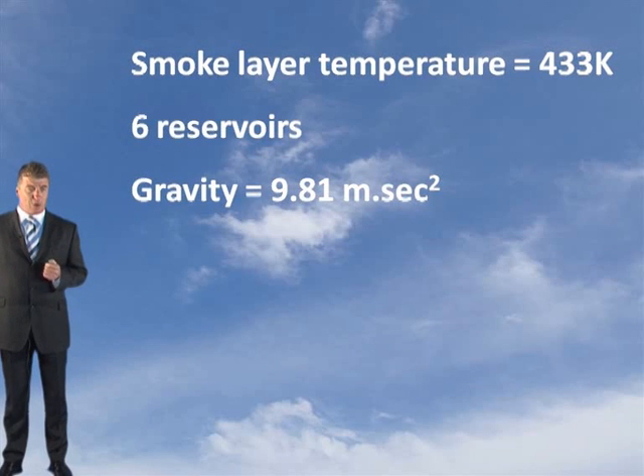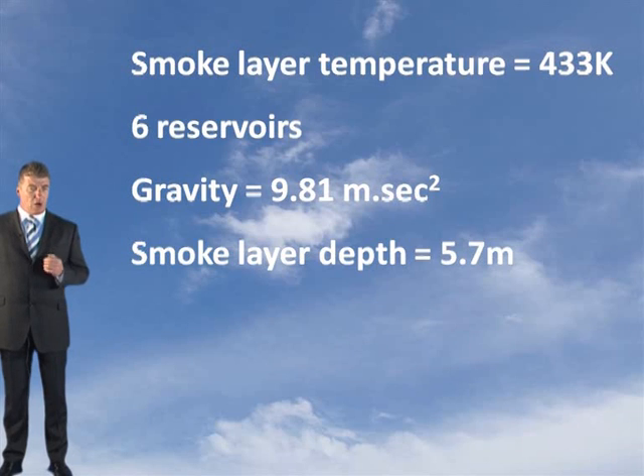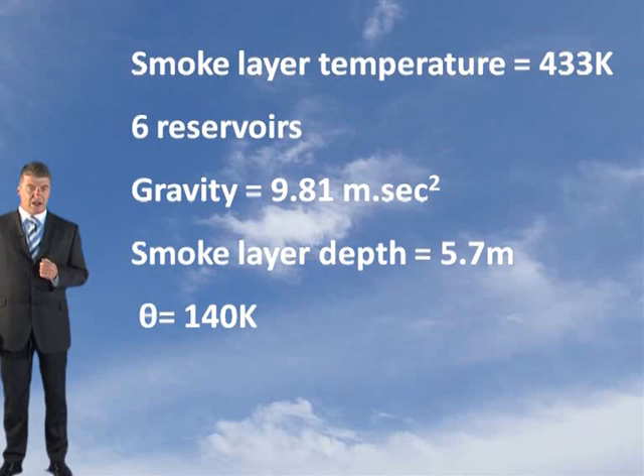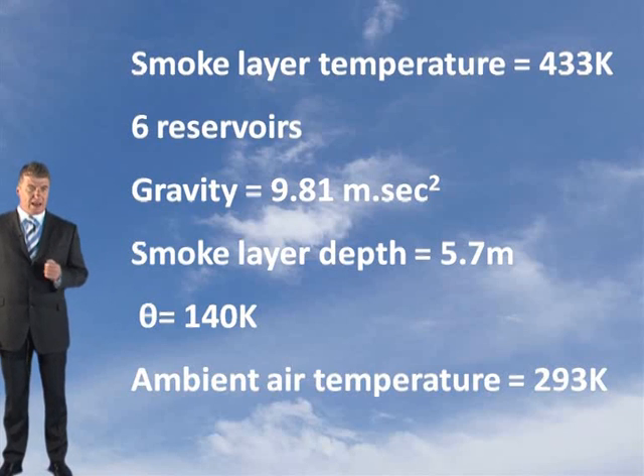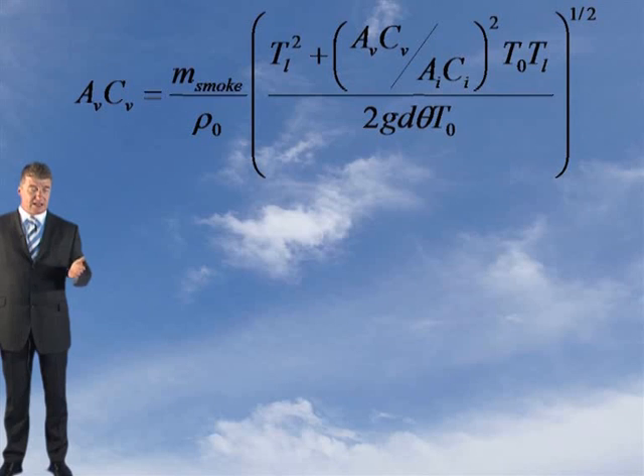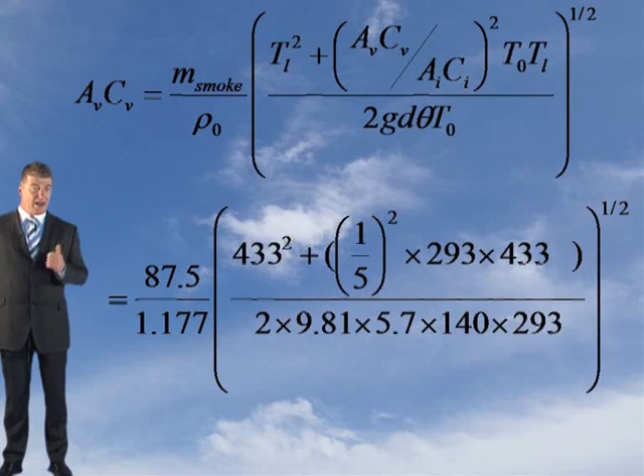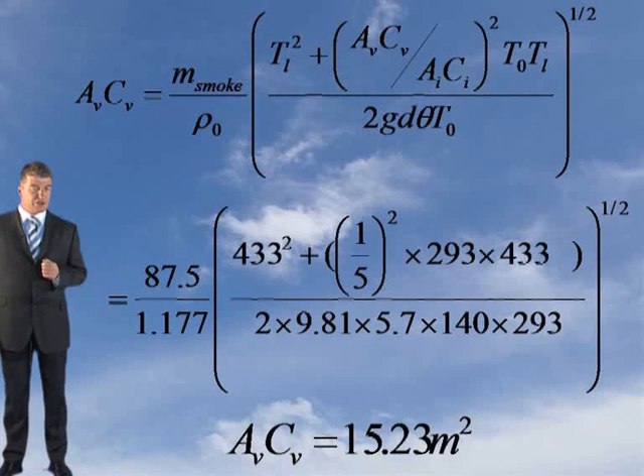Acceleration due to gravity is 9.81 meters per second squared. Your smoke layer depth is 5.7 meters. You've got a theta value of 140 degrees Kelvin. Your ambient air temperature can be taken as 293 degrees. Put them into this formula, as you can see here, and you should get an AVCV factor of approximately 15.23 square meters.